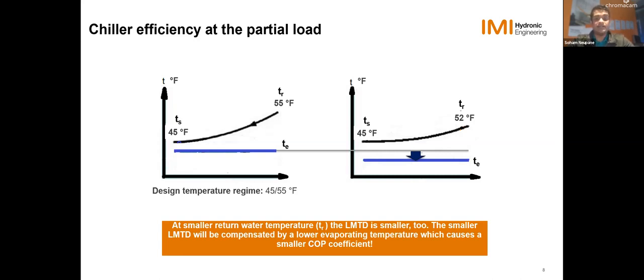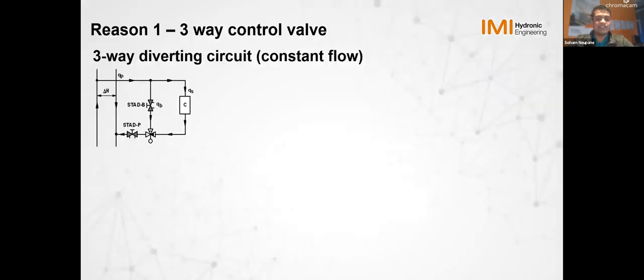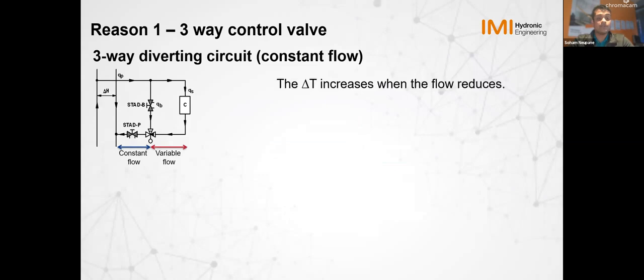So some of the main reasons that are causing this, let's look at those. The first one is three-way control valves, like a diverting circuit with constant flow, which was more common in the past, not as much now, but that's one of the main reasons you see delta T issues. So what happens is you have a bypass. The delta T basically increases when flow reduces. So if you are sending less water into the coil, it's got to spend more time to heat or cool your air, so you're going to see an increase in delta T.